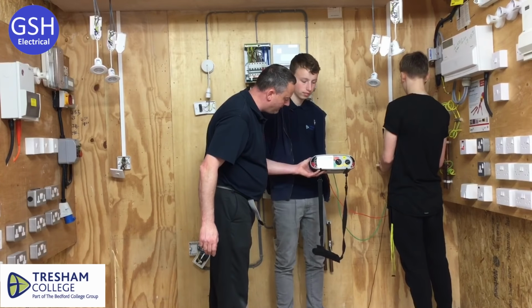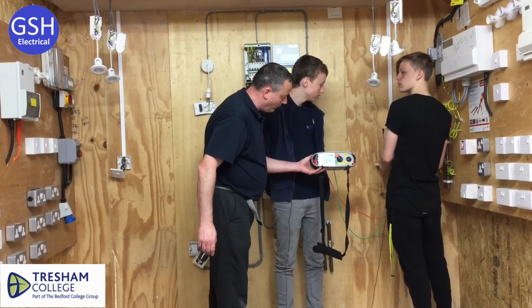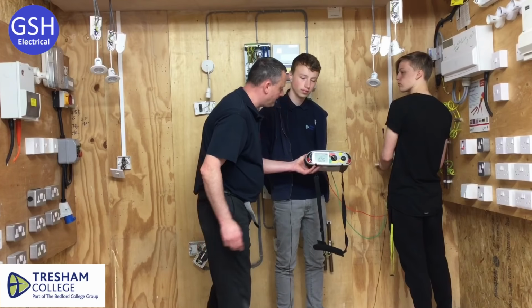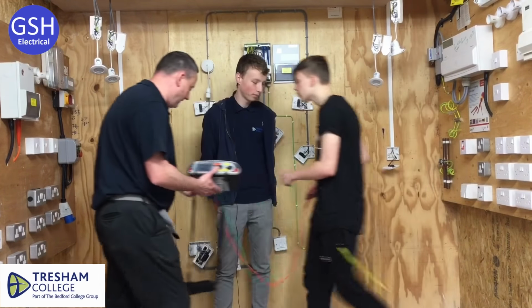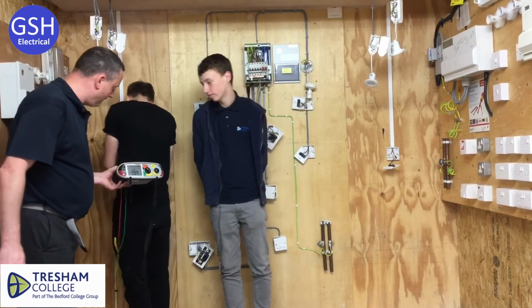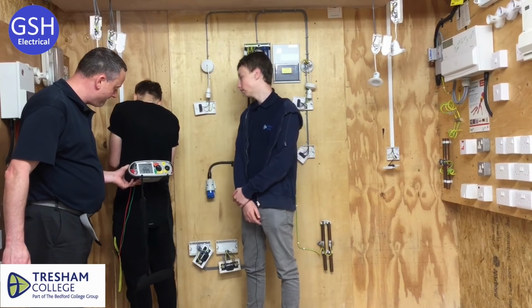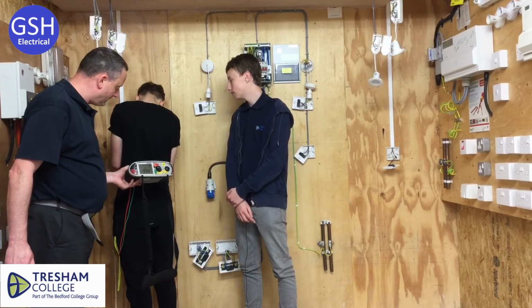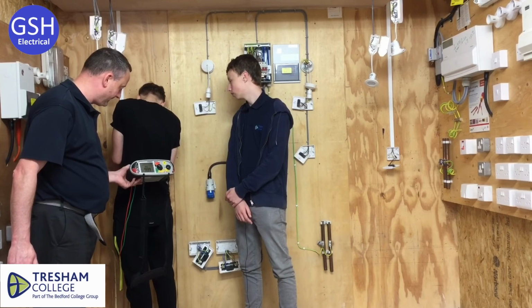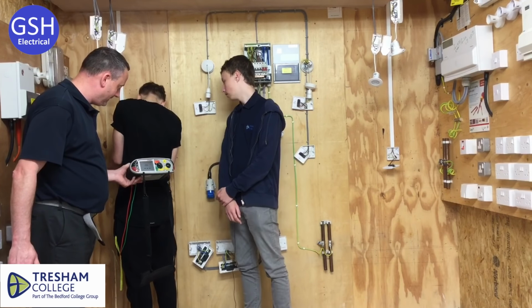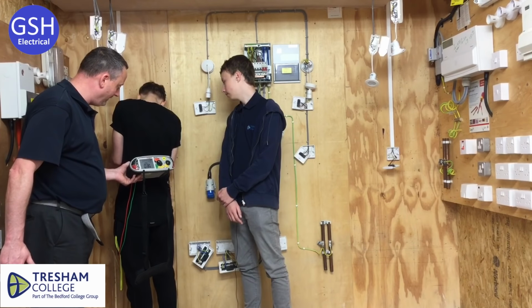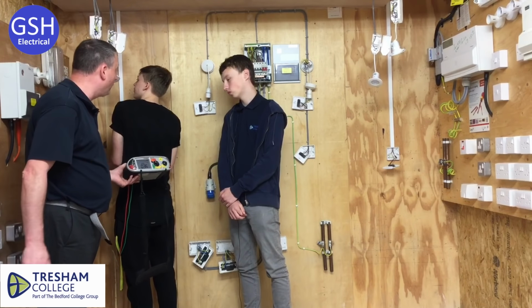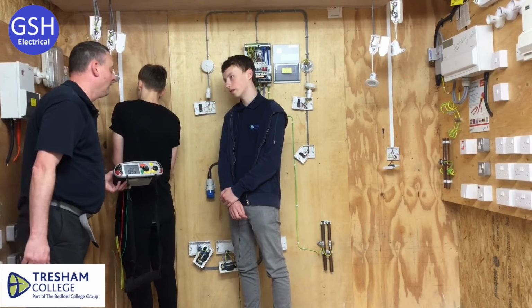Let's have a look at these readings then for the viewing public. Have we got a reading now on the CPC? 0.26. Let's move to the next switch. Okay, so across we go. Try and move everything out of the way and see what we get on this one. 0.36. Of all the readings we get, Logan, which one are we going to record? The highest.